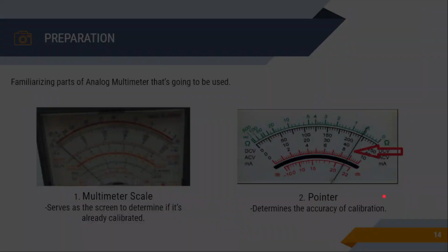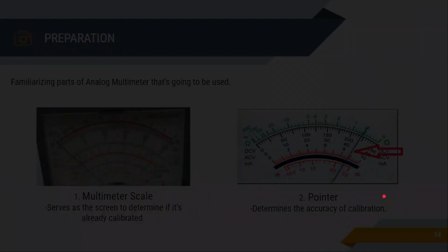Before we start on calibration, we have to prepare first and familiarize the parts of the analog multimeter that we're going to use. So here is the multimeter scale. It is very important, for it serves as the screen to determine if it's already calibrated. Second, the pointer, which determines the accuracy of calibration. Third, the selector knob, the one that I discussed earlier. This is very important. It is used to select the range that you want to calibrate. This is the times 1, times 100, times 1K, and so on and so forth. So that's the ohm range.